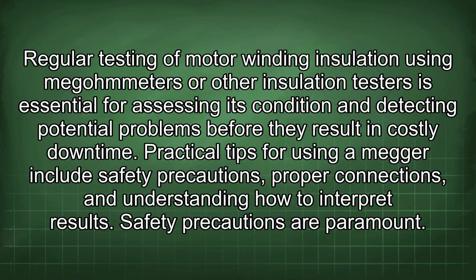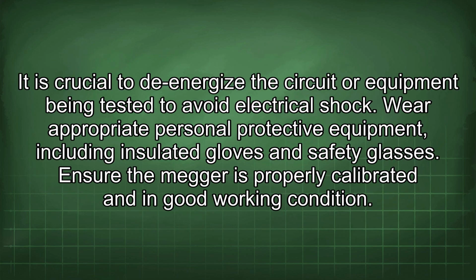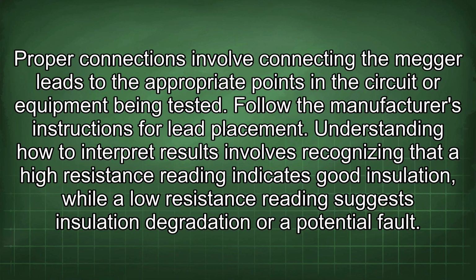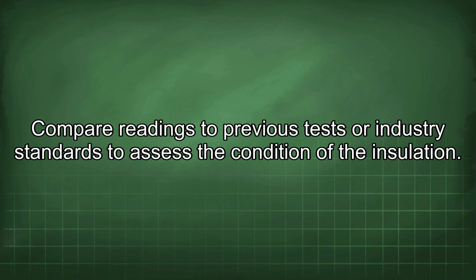Practical tips for using a Megger include safety precautions, proper connections, and understanding how to interpret results. Safety precautions are paramount. It is crucial to de-energize the circuit or equipment being tested to avoid electrical shock. Wear appropriate personal protective equipment, including insulated gloves and safety glasses. Ensure the Megger is properly calibrated and in good working condition. Proper connections involve connecting the Megger leads to the appropriate points in the circuit or equipment being tested. Follow the manufacturer's instructions for lead placement. Understanding how to interpret results involves recognizing that a high resistance reading indicates good insulation, while a low resistance reading suggests insulation degradation or a potential fault. Compare readings to previous tests or industry standards to assess the condition of the insulation.